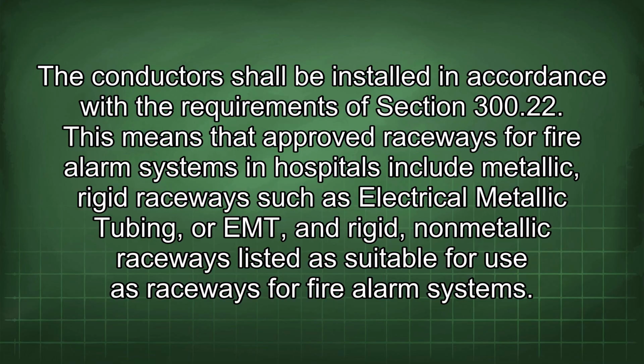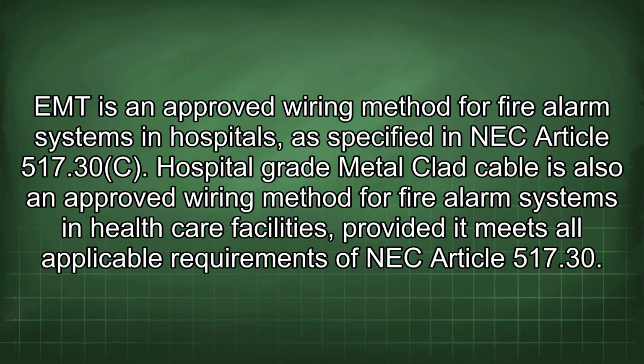This means that approved raceways for fire alarm systems in hospitals include metallic, rigid raceways such as electrical metallic tubing, or EMT, and rigid, non-metallic raceways listed as suitable for use as raceways for fire alarm systems. EMT is an approved wiring method for fire alarm systems in hospitals, as specified in NEC Article 517.30c.